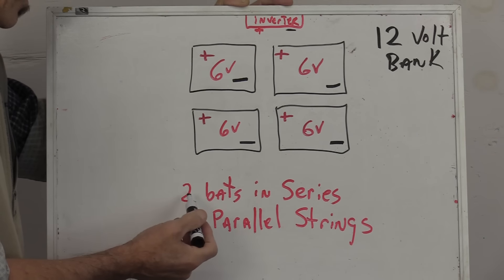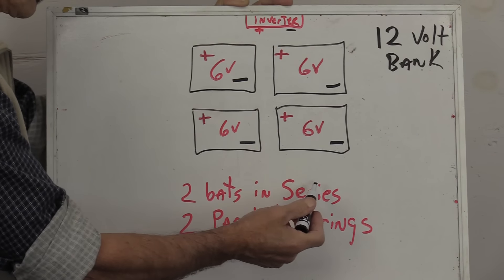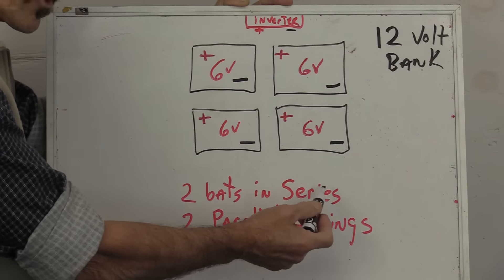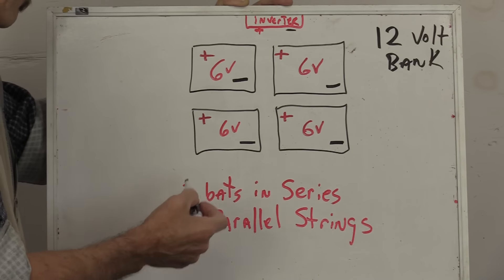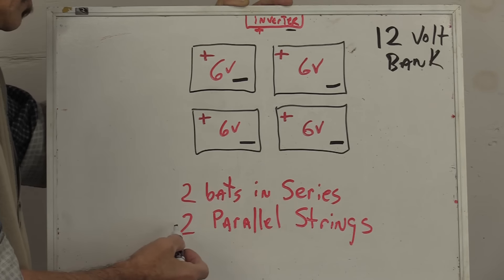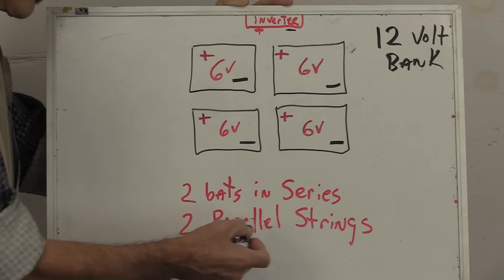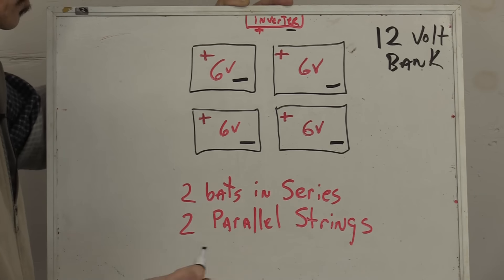What we're going to do is tie two batteries in series, two six volt in series that will equal 12 volt battery. Now we've got several banks of those and we want to tie them all in parallel strings. So this is basically how you do it.